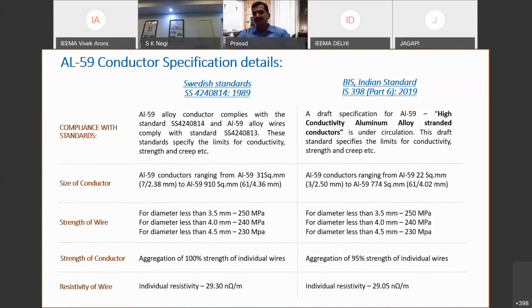So we can assure all state utilities that you will be getting the best quality of AL59 conductors for your transmission network, and it will make the existing system more robust in terms of strength and in terms of higher power transmission capabilities. The last point we would like to focus on is the resistivity of the wire. As per the Swedish specification, it can be 29.3 nano ohm per meter, whereas the individual wire resistivity in the IS standard is 29.05. So here also our Indian specification has tried to improve on industry practice, based on strength and at the same time on resistivity.